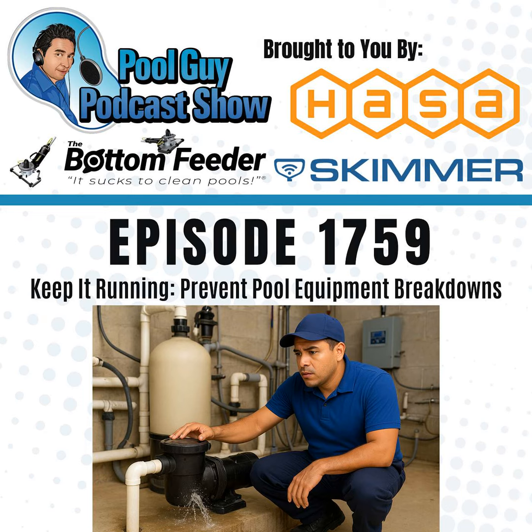Now, you can pull that off, take it to a motor shop and have the bearings rebuilt. It just depends on how old the motor is, because they have to get the shaft off and the bolts off of it. If it's really old, they can't take the motor apart to replace the bearings, so it's a shot. If you look at the motor and there's no paint left, it's all rusted, chances are they're not going to be able to rebuild the bearings. And they can do that. They usually give you a 6-month guarantee on it. Some give you a 3-month guarantee.